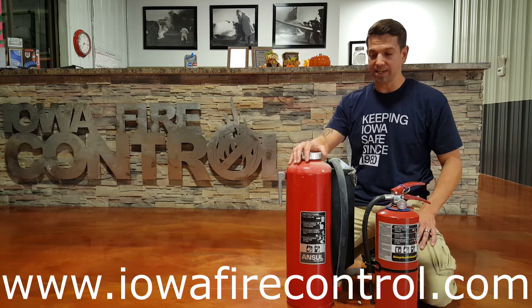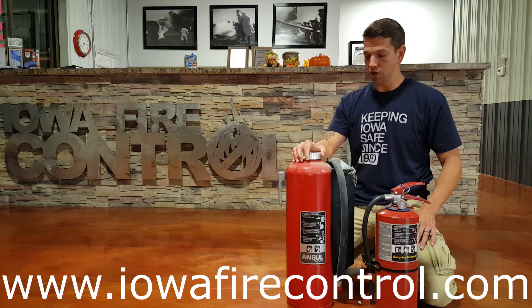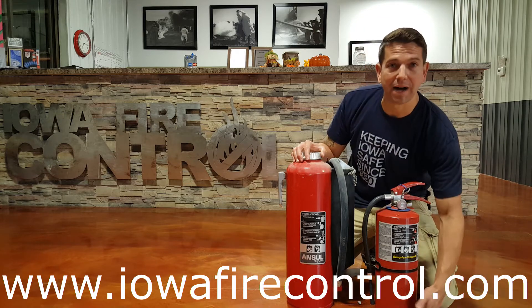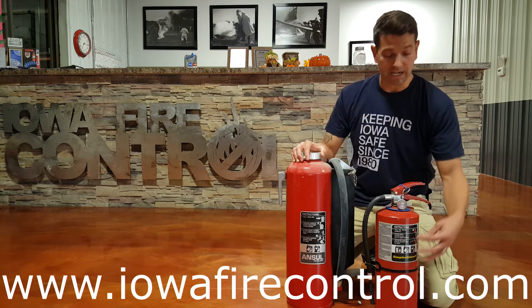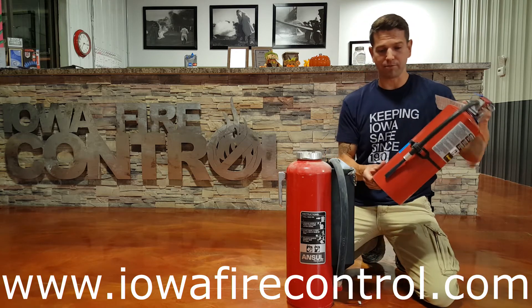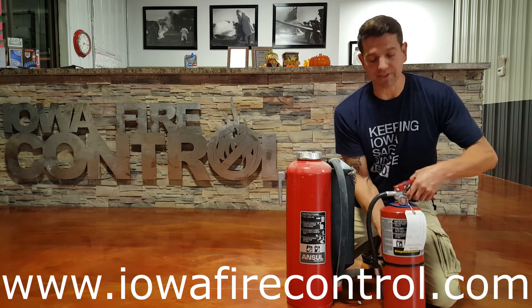The other reason that I like the cartridge operated is it's super durable. If you drop this thing while standing it up on its side, it's not going to dent the bottom, it's not going to dent the side. For those of you that know anything about fire extinguishers, with the stored pressure type, if you drop it — if I was to drop it from right here — it's probably done. You're going to have to condemn it.